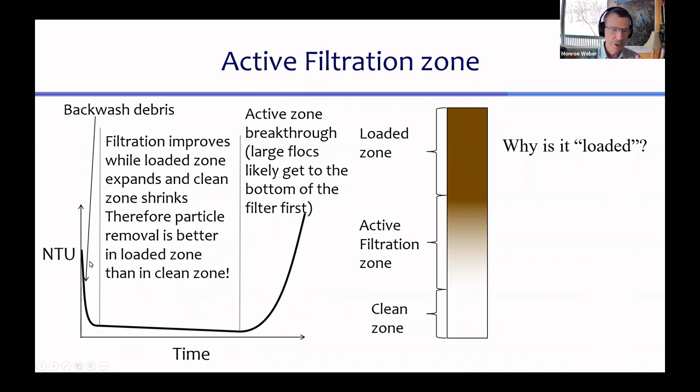There's this initial period when performance is bad. It's a combination of backwash, debris that was left from the previous time the filter was clean that might be coming out initially. And there's something about the filter loading and having something about it that's making performance better than if it were just clean sand.